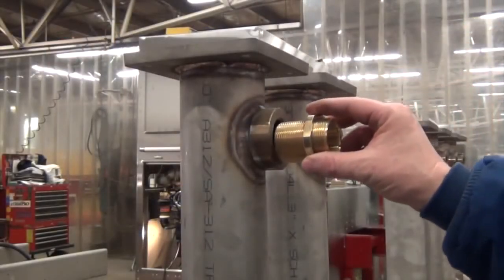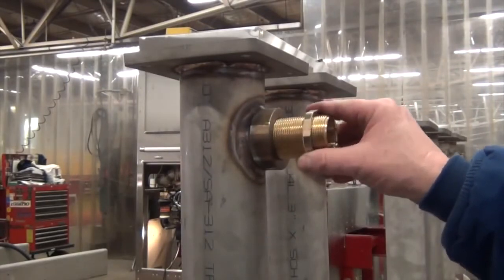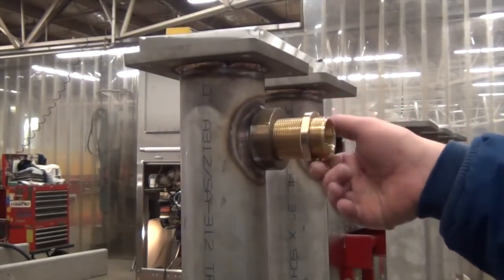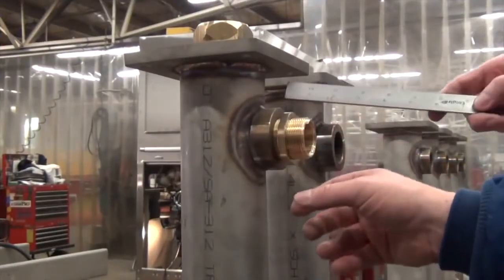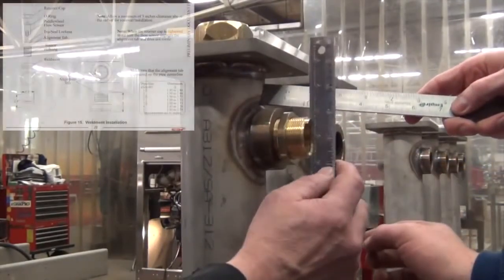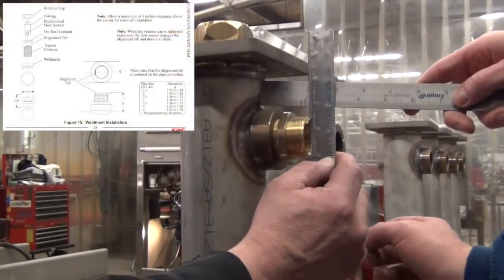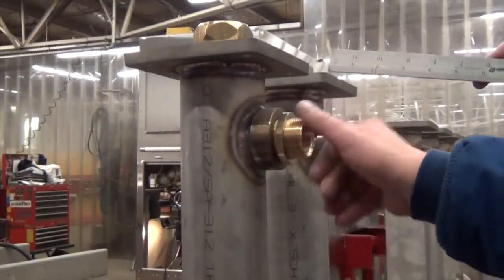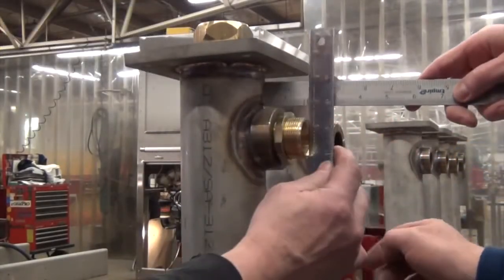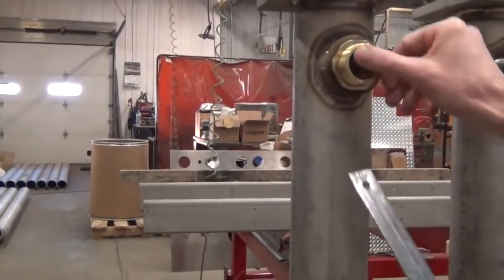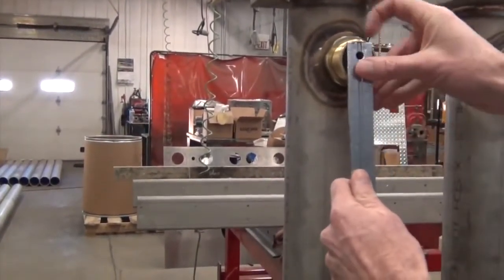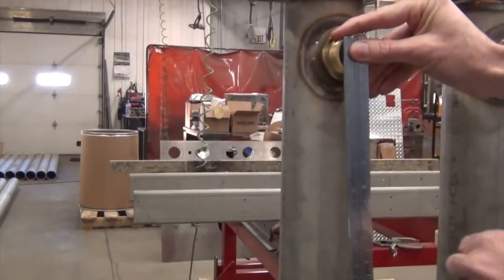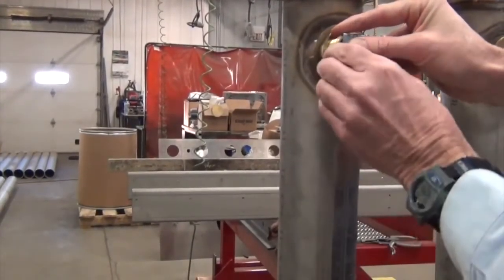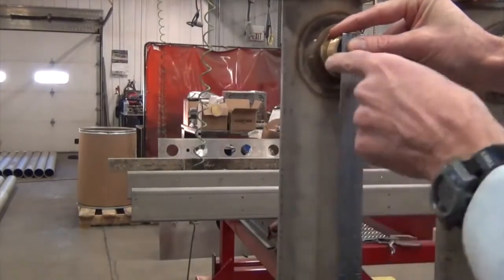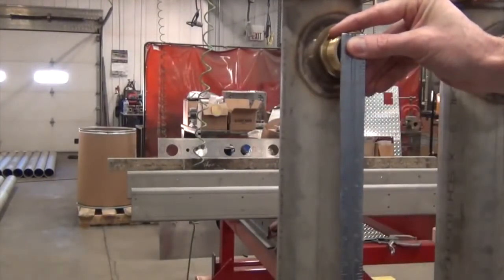In this example, we have used a weldment. The depth of the sensor housing is critical and depends on the size of the pipe that you are using. Consult the installation manual for the correct depth required for your application. The alignment tab must be centered on the pipe center line. It can be either upstream or downstream, but must be on the center line. You can use a ruler pressed against the alignment tab to help find the pipe center line.